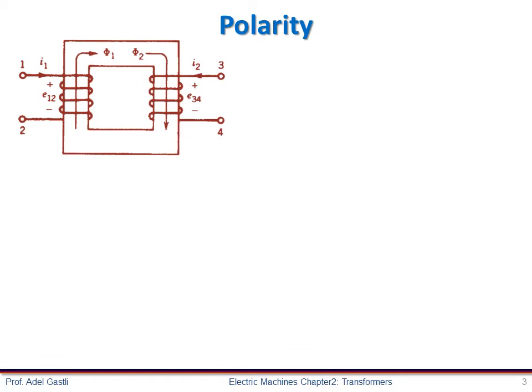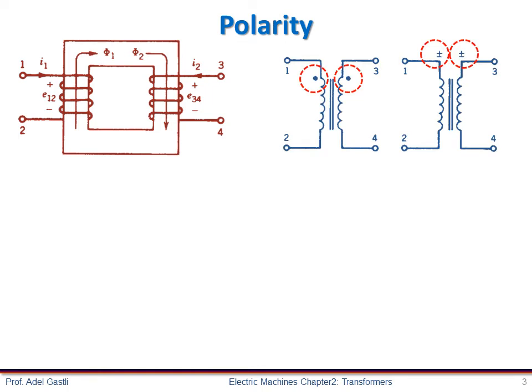Another important feature or characteristic of the transformer is the polarity of its windings. The polarity of transformer windings designates the relative instantaneous current directions of winding leads. The polarity of windings is usually designated or marked with either dots or plus/minus signs, as shown in this figure. These markings may be found on transformer cases, beside terminals, winding leads, nameplates, or schematic diagrams.